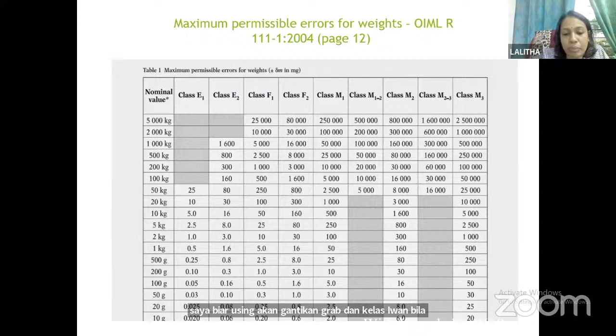This is the table that I took, the standard weight permissible error. All of us will have a standard value. All the companies will give us a standard value when they are doing a standard calibration. This is one example. Let's say we are using 10 gram, then class E1 will have this error that we can use, and so on for class E2 and class F1.